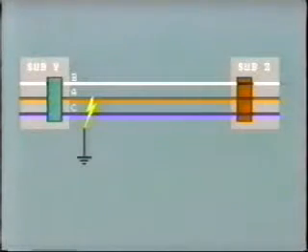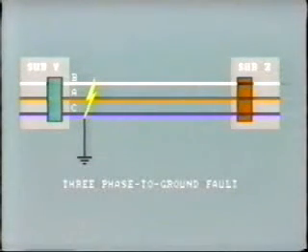At this point, the fault again changes. The A phase conductor now burns open. The tree contacts B phase and falls to the ground. But all three open conductors are now in contact with ground, resulting in a three-phase to ground fault.